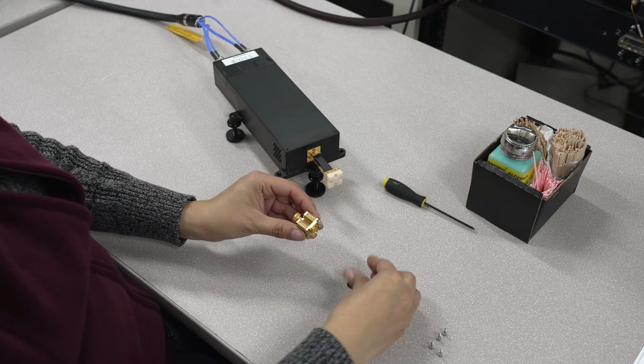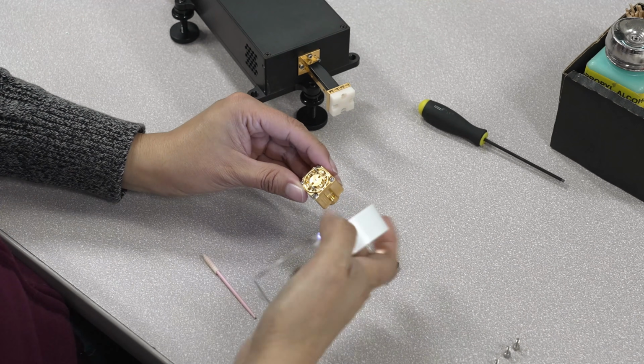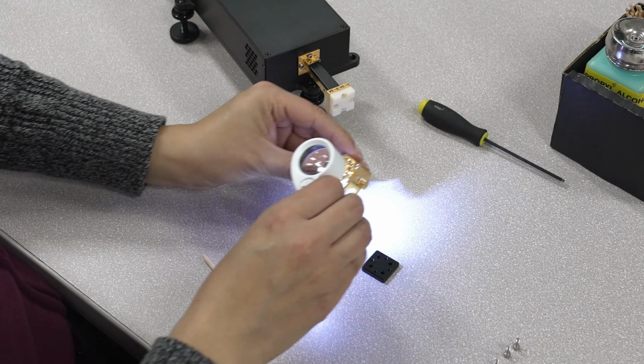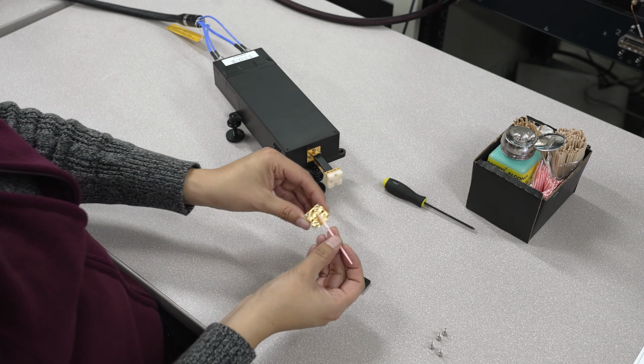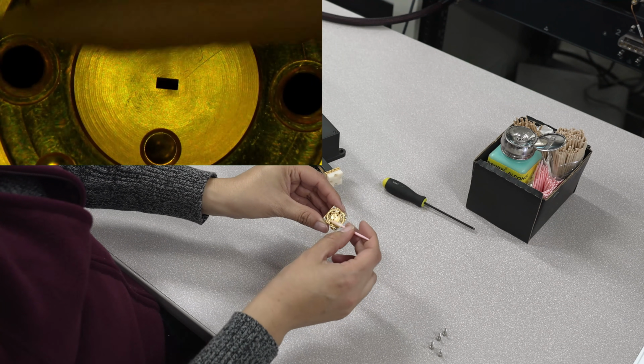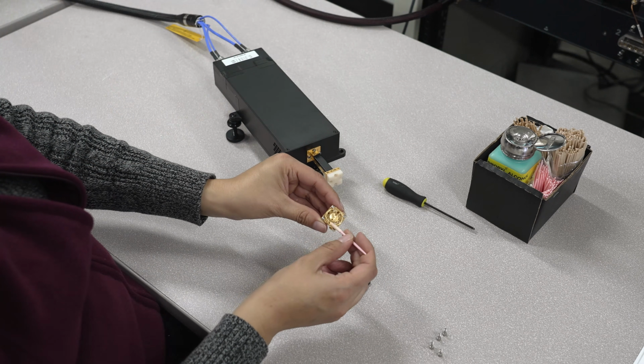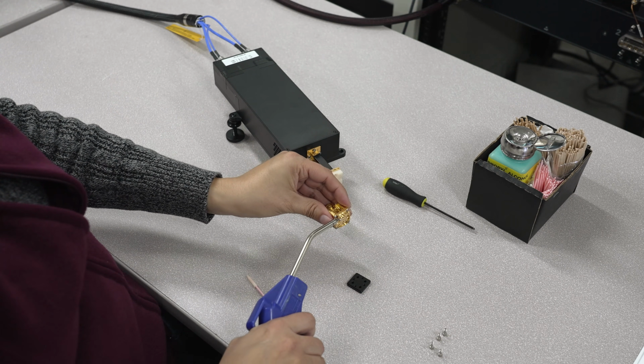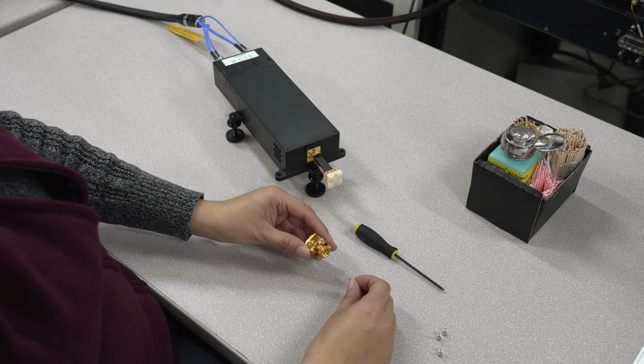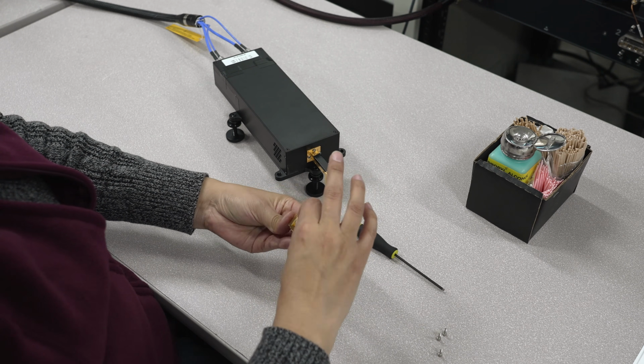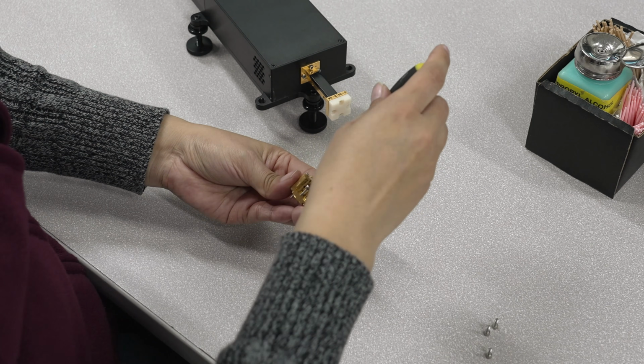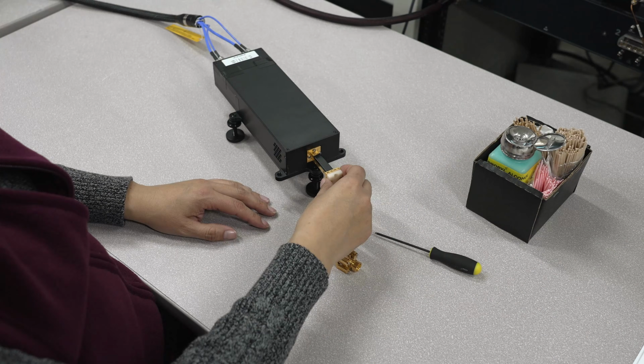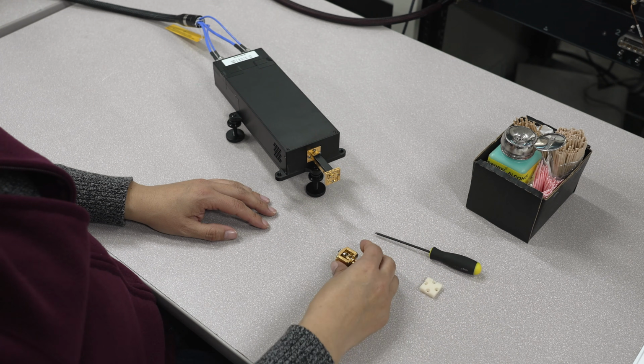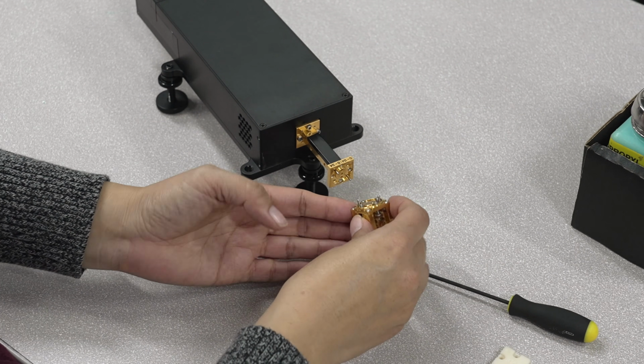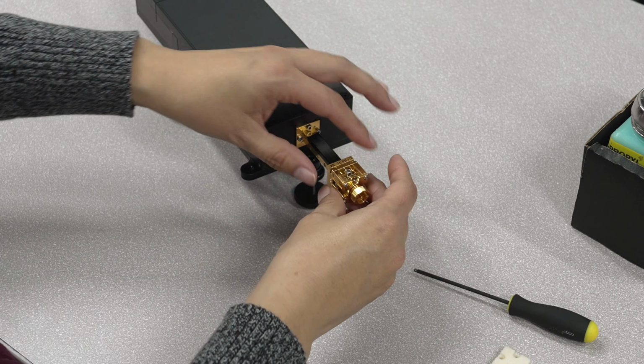For waveguide to 0.5 mm coaxial adapters, remove the protective covers, inspect with a microscope or the eye loupe, and clean. For the waveguide interface, use a foam swab dipped in isopropyl alcohol. Apply compressed air parallel to the part to avoid blowing air directly into the rectangular aperture. Use a 3/32 inch hex screwdriver to connect the screws. To connect the device to the test port, ensure both apertures and dowel pins are aligned. Then use a screwdriver to tighten the screws to finger tight in an X pattern as shown.